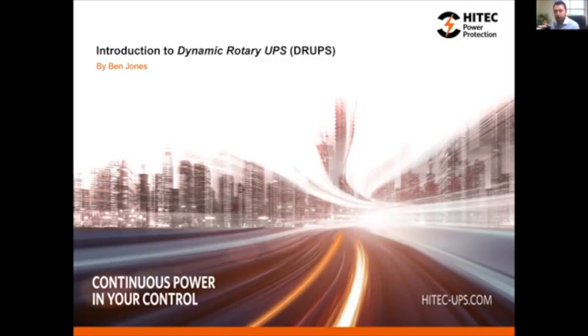We've got examples and case studies of all types of loads, quite dirty mechanical loads, very high harmonics. I'm getting into too much detail here, but if you have a system with really heavy harmonics, we can actually change the impedance of the alternator and the reactance of the choke to accommodate that. Typically it just requires us to know, but I can't think of many scenarios.